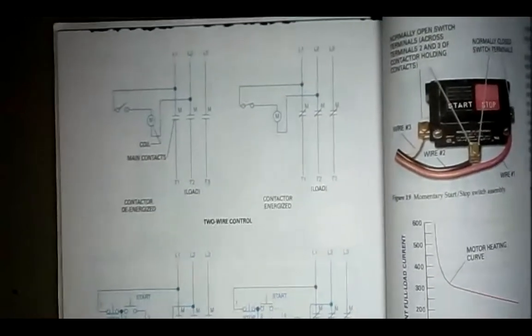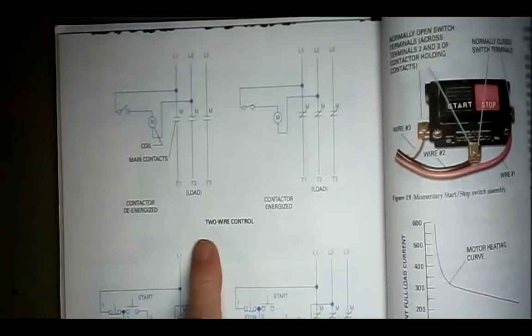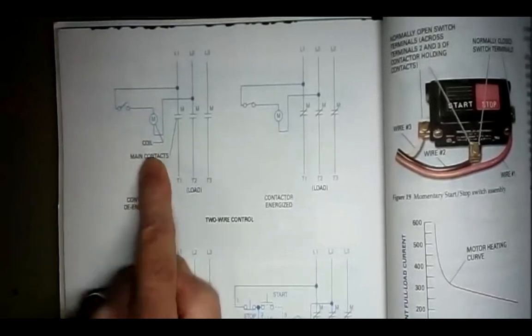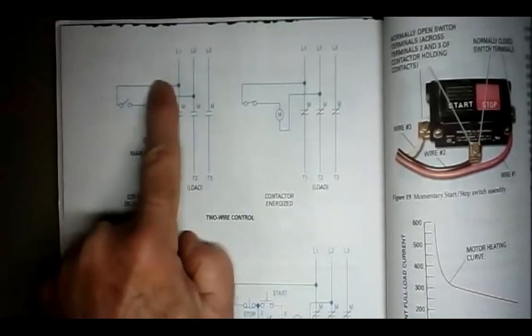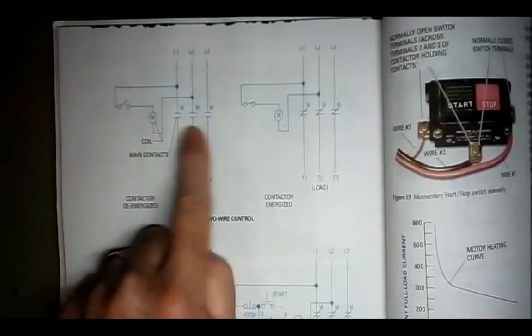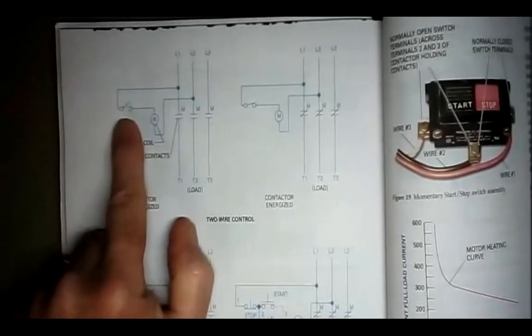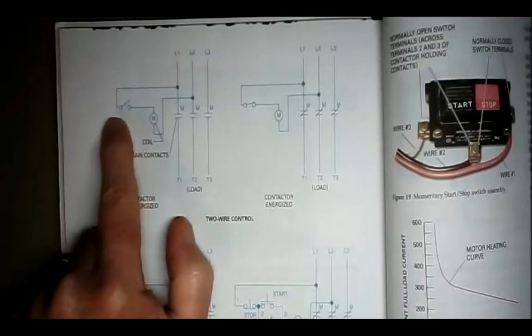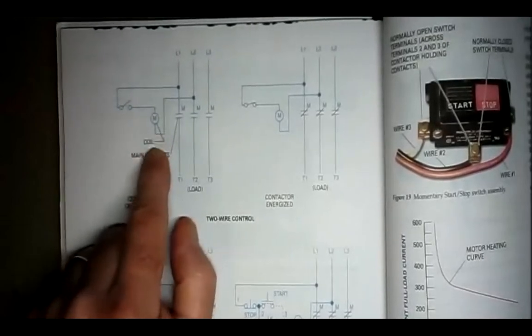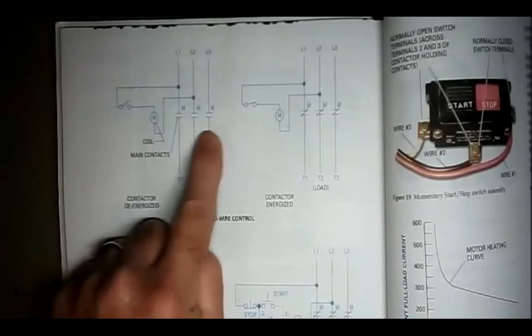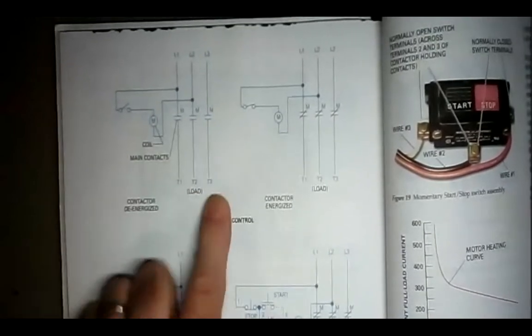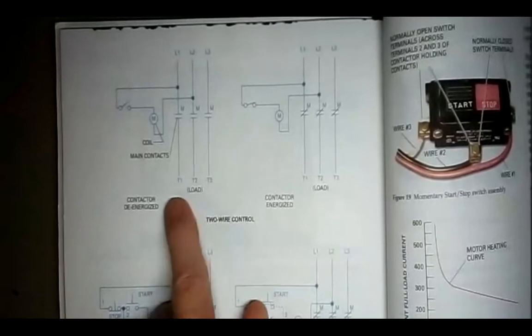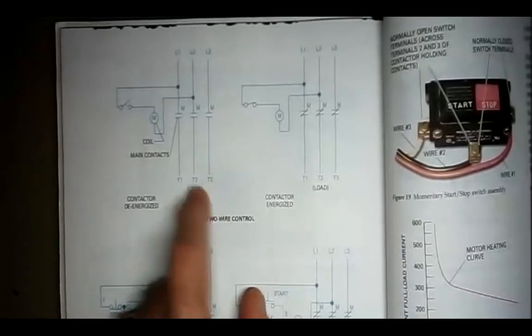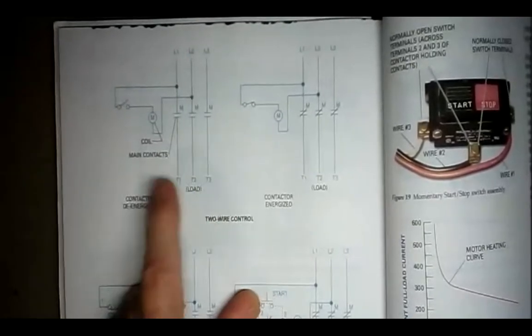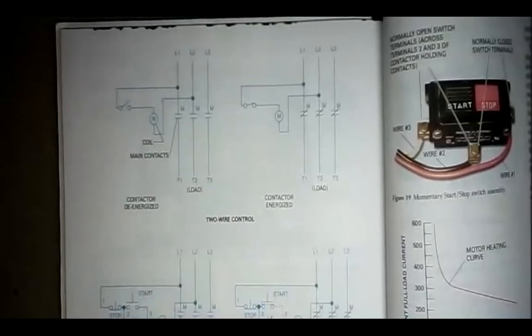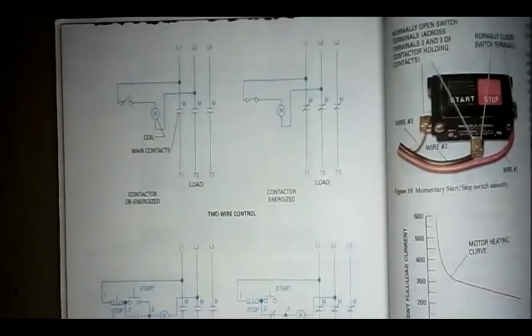Here on page 16, they're showing us more schematics. It's showing that the coil voltage sometimes comes off of line 1, line 2 before the contacts. So if you went through a switching device, that 480 volts would cause that coil to energize, and it would close these contacts, and then you'd start the motor, T1, T2, T3. The T leads go to the motor. Line 1, 2, and 3 come in, T1, 2, and 3 go out. They're the T leads. Okay.